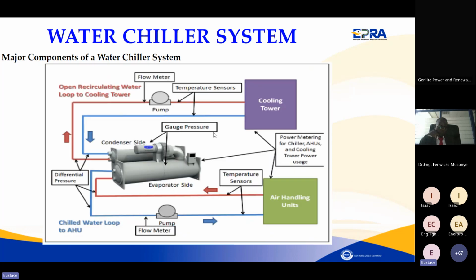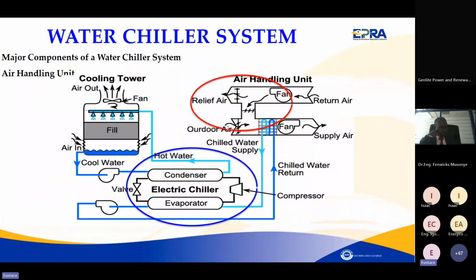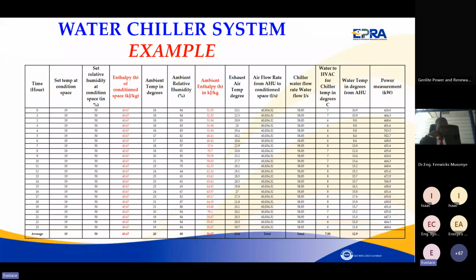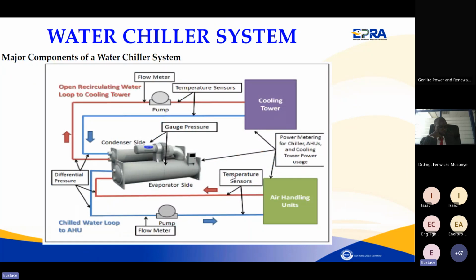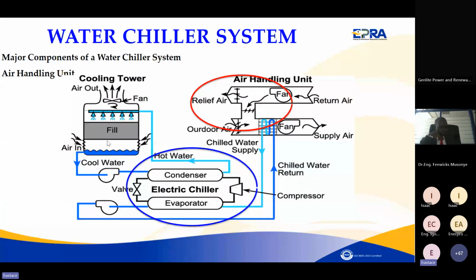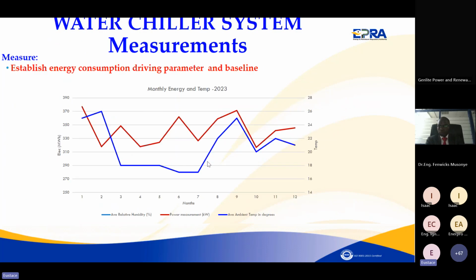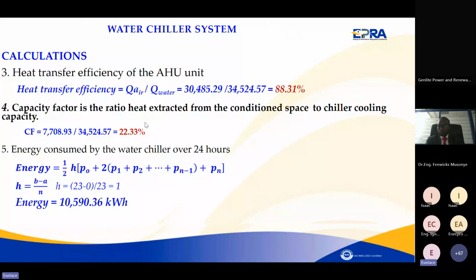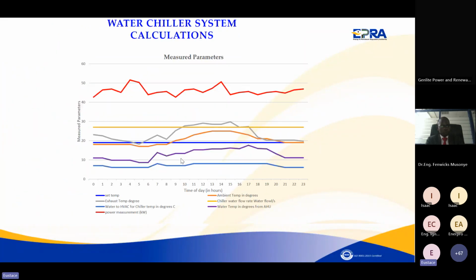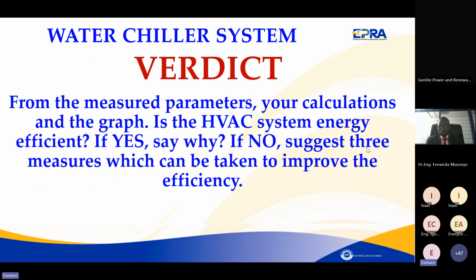If the temperatures are very low here, and that one can also be seen from the data, you find the temperatures most of the times are between 20, 23, like at night, they are 19, 20, and so on. So in that case, it means I'm still running the chiller, generating a lot of cooling, which is not required. So probably I should have switched off. So make sure when you get the capacity factor or the load factor, it tells you a lot. So the system automatically is not efficient.